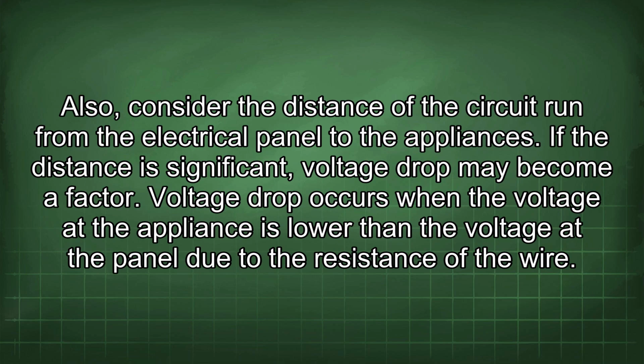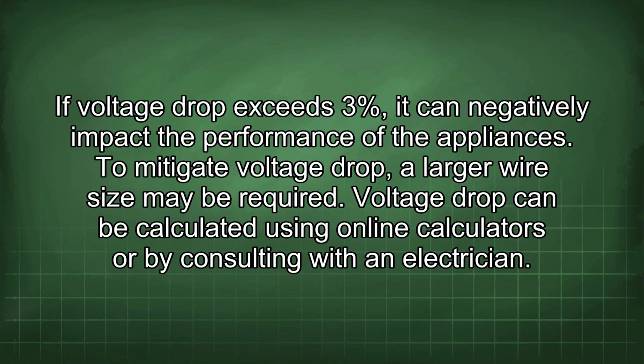If the distance is significant, voltage drop may become a factor. Voltage drop occurs when the voltage at the appliance is lower than the voltage at the panel due to the resistance of the wire. If voltage drop exceeds 3%, it can negatively impact the performance of the appliances. To mitigate voltage drop, a larger wire size may be required. Voltage drop can be calculated using online calculators or by consulting with an electrician.